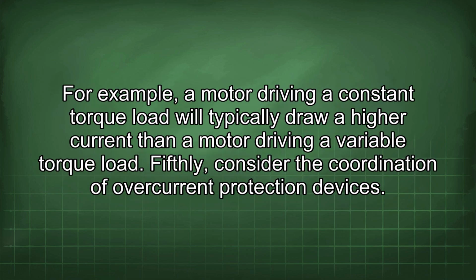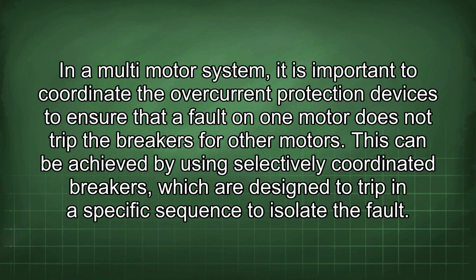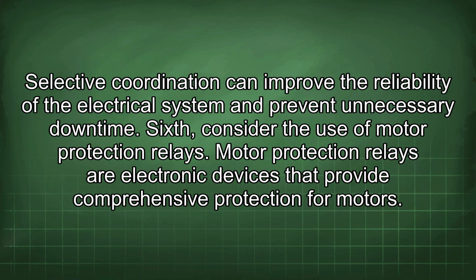For example, a motor driving a constant torque load will typically draw a higher current than a motor driving a variable torque load. Fifthly, consider the coordination of overcurrent protection devices. In a multi-motor system, it is important to coordinate the overcurrent protection devices to ensure that a fault on one motor does not trip the breakers for other motors. This can be achieved by using selectively coordinated breakers, which are designed to trip in a specific sequence to isolate the fault. Selective coordination can improve the reliability of the electrical system and prevent unnecessary downtime.